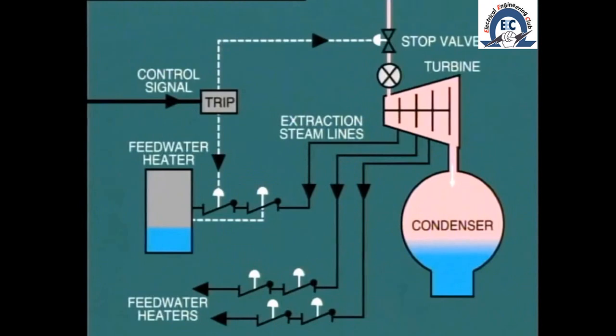A similar problem can occur with entrained steam feeding back into the turbine from extraction lines. To prevent this, positive-closing non-return valves are installed and arranged to close when the turbine is tripped. The valves are actuated pneumatically but are controlled by a hydraulic trip relay.